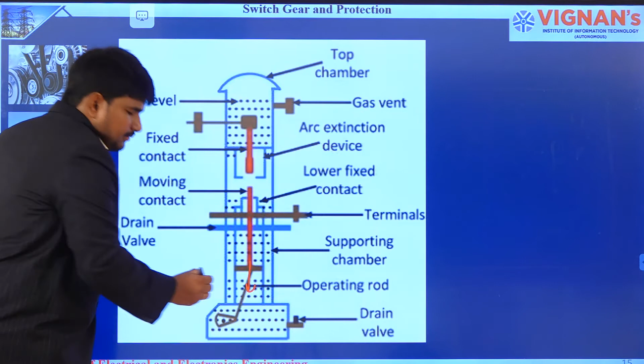Okay, we need to quench this arc as usual. Further, in the minimum oil circuit breaker, what happens here is this oil is there now. This oil will be coming here and also this oil. So the total oil and vaporized hydrogen, because of this heating, hydrogen will also be produced. The oil and hydrogen will be pressurized here and then the arc will be quenched.